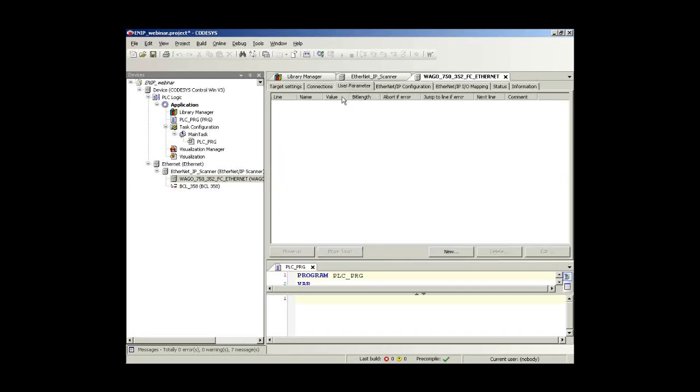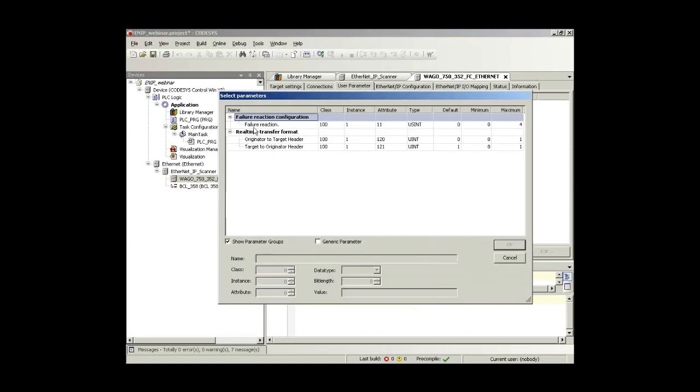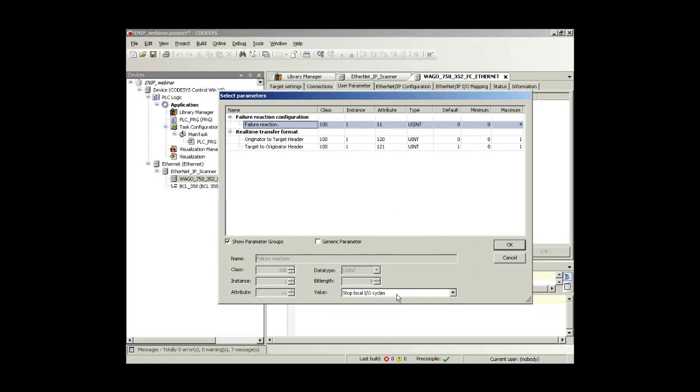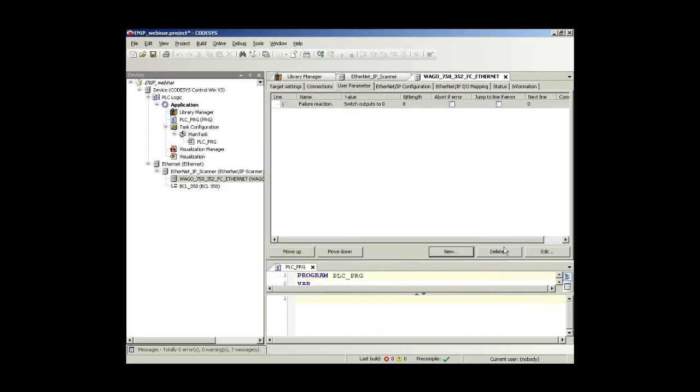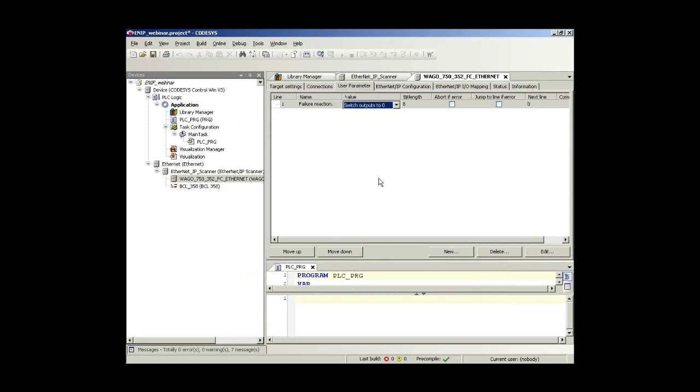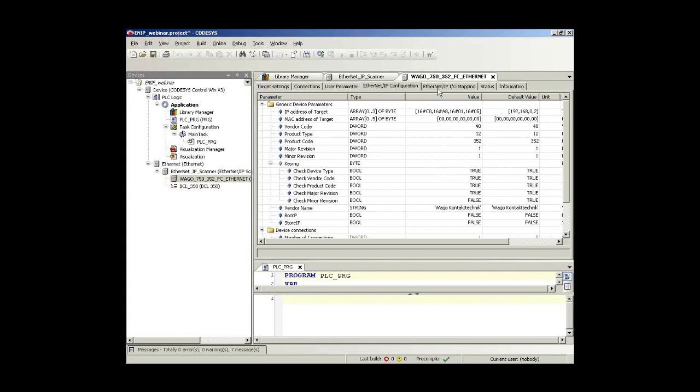Let's go to the third register card. There we have the possibility to add user parameters. This adapter offers some user parameters, for example like a failure reaction. I could configure that in case of an error or a failure, all local IOs are stopped or I switch all outputs to zero or something like that. Of course I can change that as well directly here in that tree again. Then once again we have here a register card showing all implicit variables of the EtherNet/IP configuration. This is an information for the professionals among you who might have a direct view on every single variable.